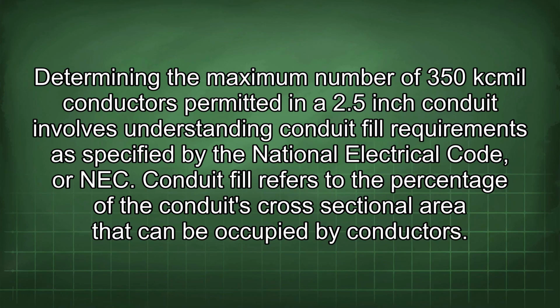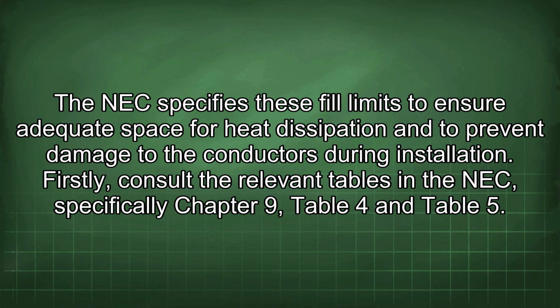Determining the maximum number of 350 kcmil conductors permitted in a 2.5-inch conduit involves understanding conduit fill requirements as specified by the National Electrical Code, or NEC. Conduit fill refers to the percentage of the conduit's cross-sectional area that can be occupied by conductors.